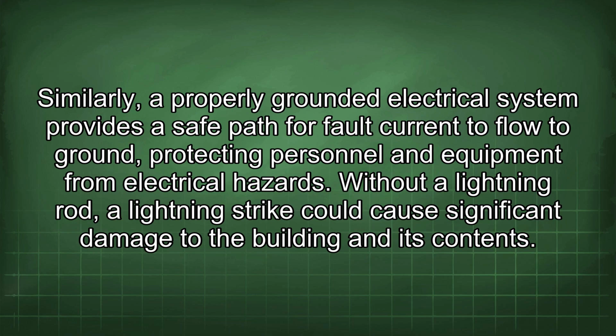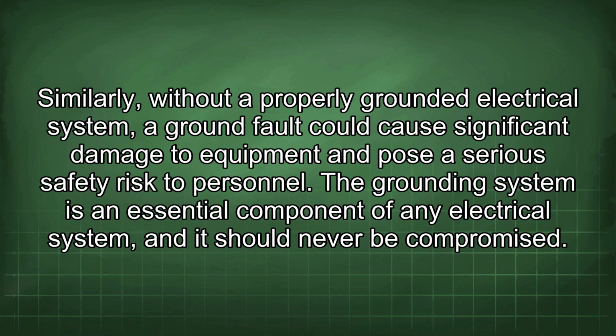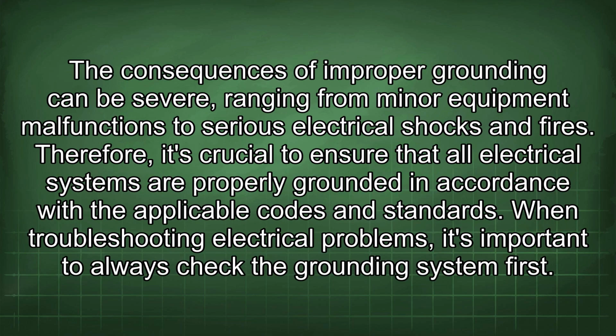Without a lightning rod, a lightning strike could cause significant damage to the building and its contents. Similarly, without a properly grounded electrical system, a ground fault could cause significant damage to equipment and pose a serious safety risk to personnel. The grounding system is an essential component of any electrical system, and it should never be compromised. The consequences of improper grounding can be severe, ranging from minor equipment malfunctions to serious electrical shocks and fires. Therefore, it's crucial to ensure that all electrical systems are properly grounded in accordance with the applicable codes and standards.